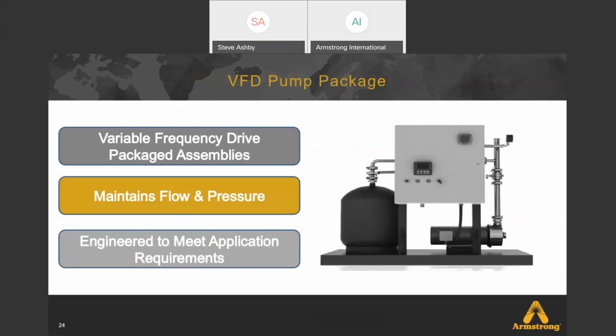Okay, your booster pumps, most of the time, this water, as it goes to the tank, then feeds a recirculated loop to your hose drops. So we need to take atmospheric water and pressurize it and move it through that hot water loop. So variable drive packages are also part of the hot water systems. This maintains flow and pressure in the hot water loop. So when hose stations are activated, they have both the pressure and the desired temperature immediately. Of course, these all change as far as capacity of the heater itself.